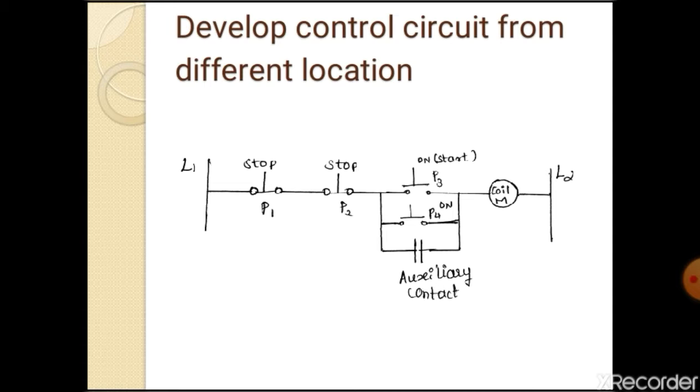So the motor starts running. After coil is energized holding contact will close and current flows. The running motor can be stopped by pushing off push button P1 and P2. When any push button is pressed coil is de-energized so that main contact gets open and motor stops.